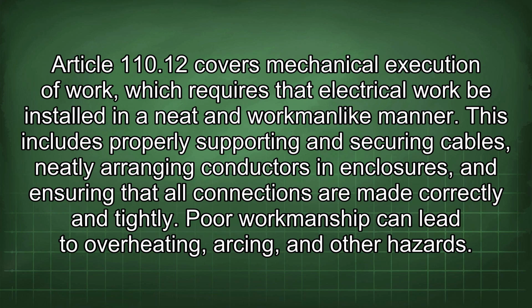Article 110.12 covers mechanical execution of work, which requires that electrical work be installed in a neat and workmanlike manner. This includes properly supporting and securing cables, neatly arranging conductors in enclosures, and ensuring that all connections are made correctly and tightly. Poor workmanship can lead to overheating, arcing, and other hazards.